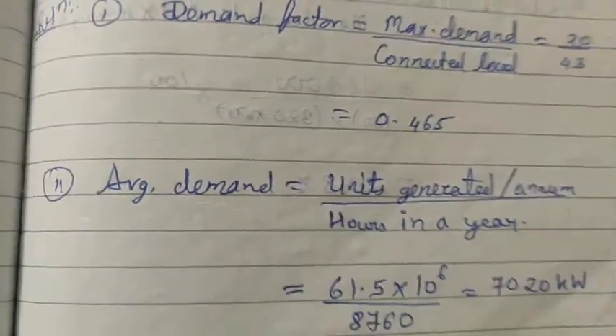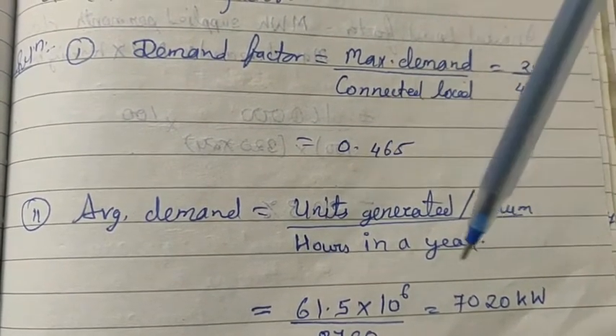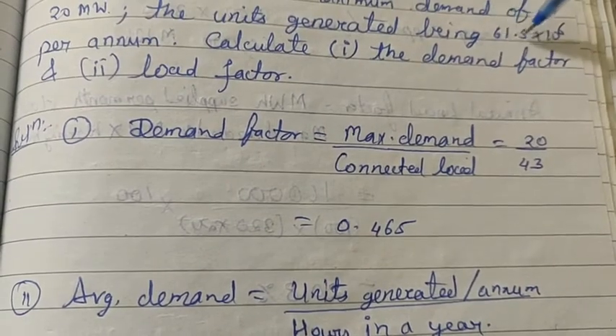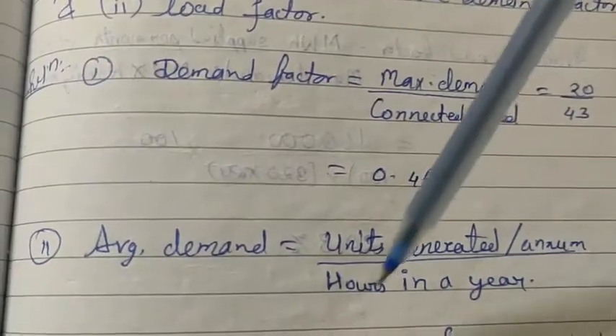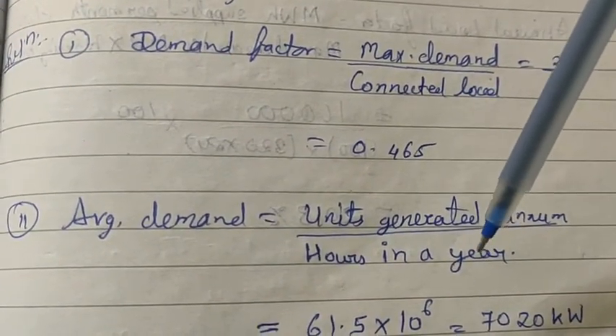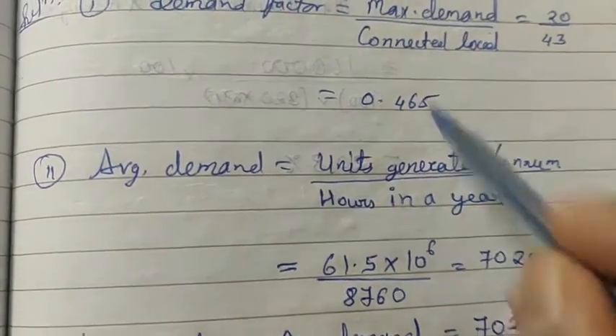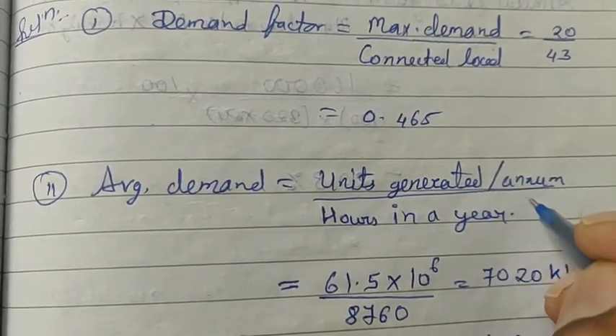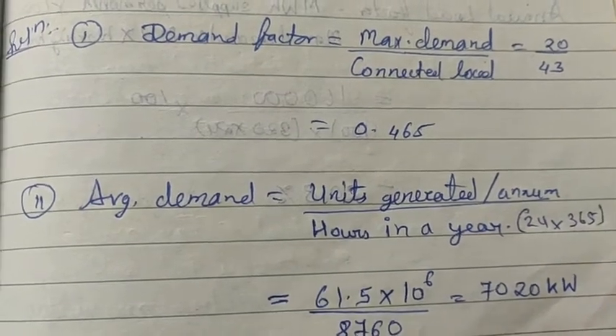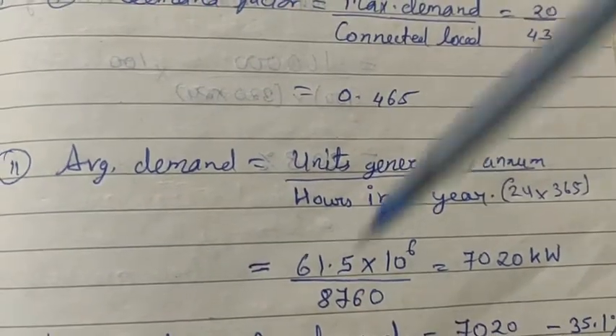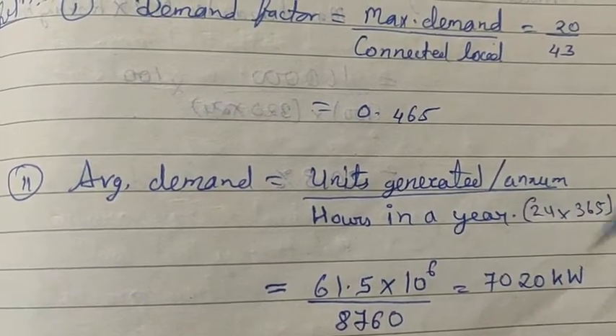Now for load factor, we first need to find the average demand. Average demand equals units generated per annum divided by hours in a year. Units generated per annum is 61.5 × 10⁶. Hours in a year is 24 × 365 = 8760 hours. Solving this, the average demand comes out to be 7020 kilowatt.